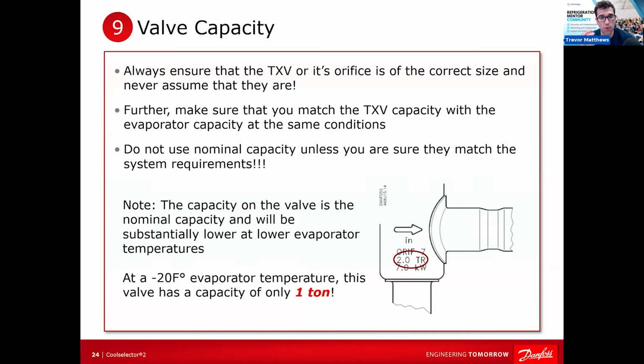What is the information they need to properly size? Because there's a lot of good softwares out there, but what do they need to size these TX valves? Make sure you put the conditions you want. So if it's a -20, you pay attention to that. So we all make guides. All right. Here's our TXV selection chart. You've usually got nominal capacity, and then you've got the refrigerant and your evaporator temperatures. So find the refrigerant, find your evaporator temperature, and you go down there until you see the first capacity that's equal to or larger than your evaporator capacity. Easiest way to start, or whatever your load is. People always say load, it makes me nervous.